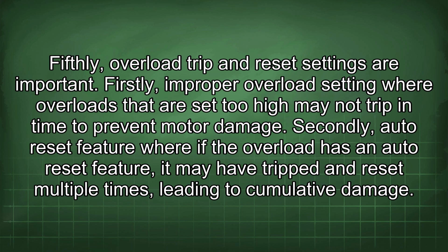Firstly, improper overload setting, where overloads that are set too high may not trip in time to prevent motor damage. Secondly, auto reset feature, where if the overload has an auto reset feature, it may have tripped and reset multiple times, leading to cumulative damage.